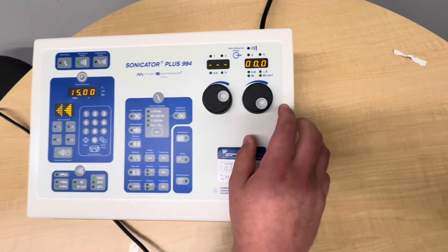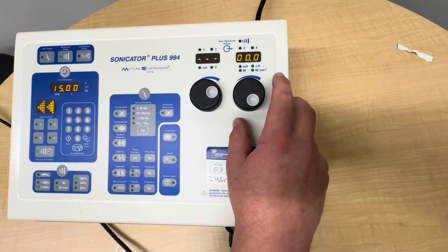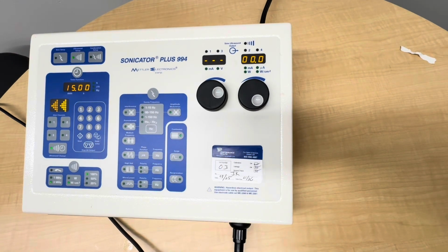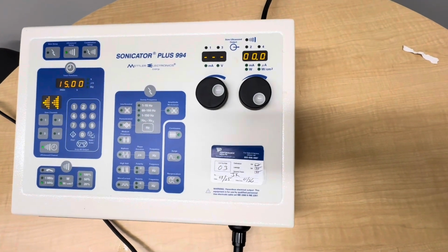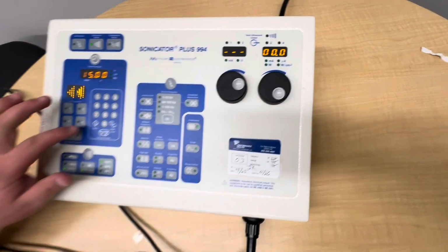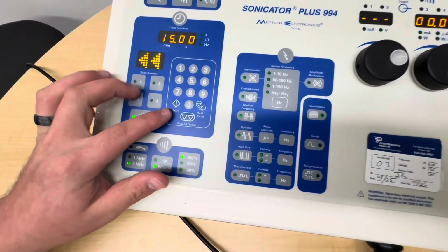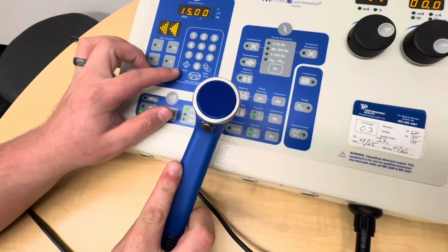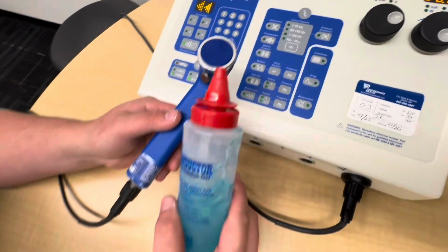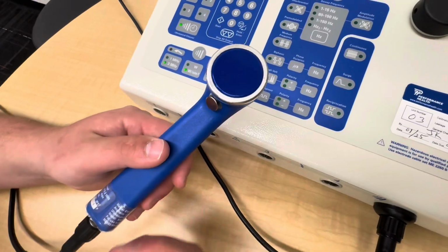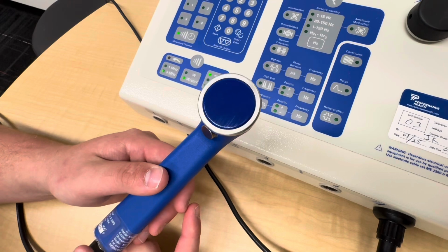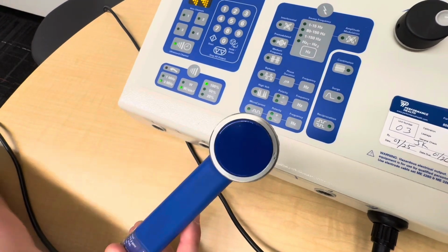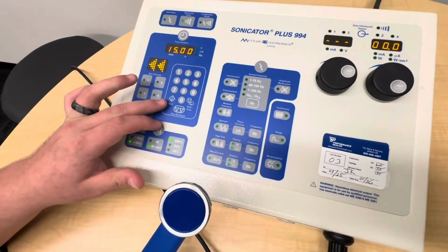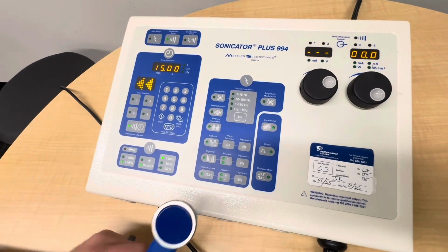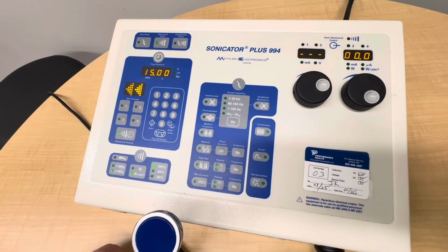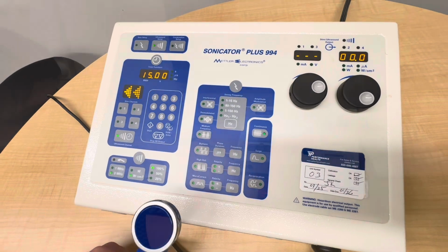Next, we have intensity. After we hit start, we can adjust the intensity anywhere from 0.5 to 2, depending upon the patient's preference. Prior to hitting the start button, make sure that we place this ultrasound with the gel on the patient so that we don't obstruct or injure or damage anything on the machine. You hit start, and then you can hit stop anytime that you need to change any of the settings, such as intensity.